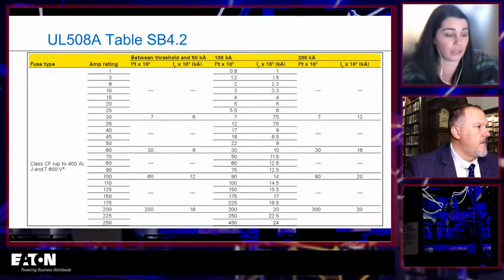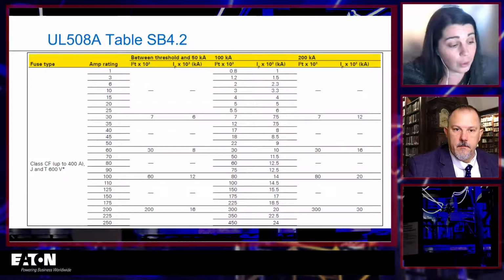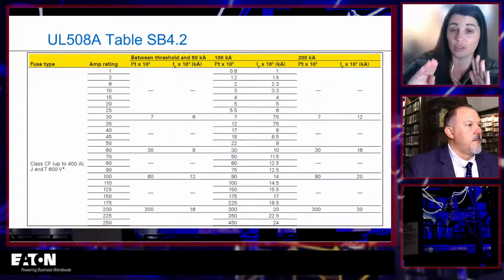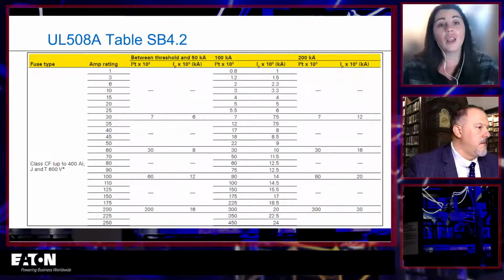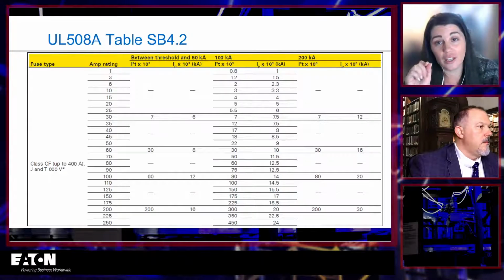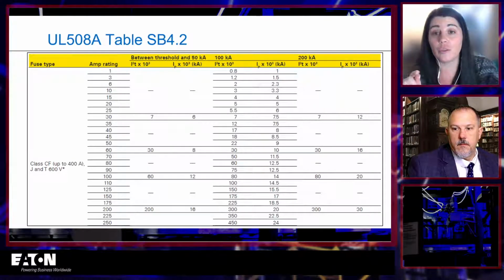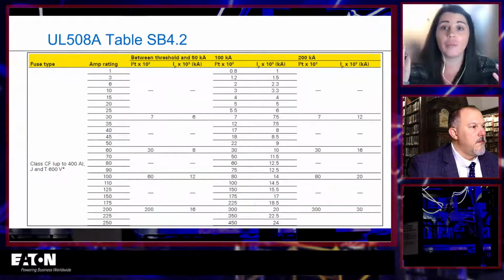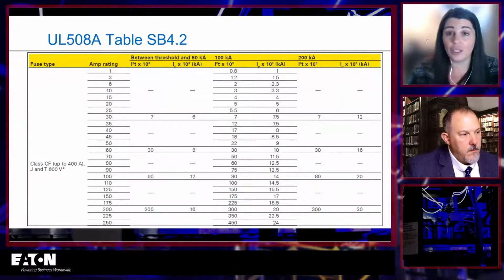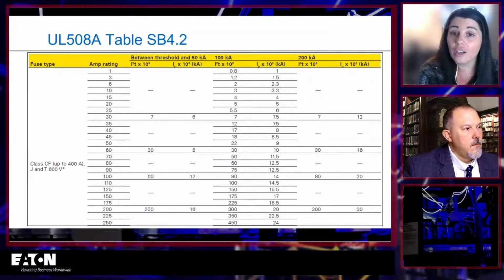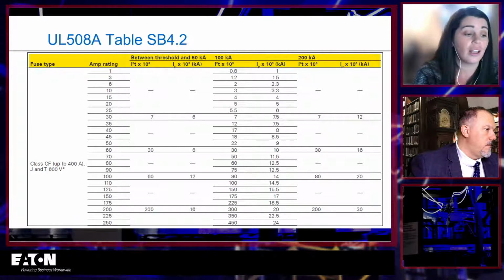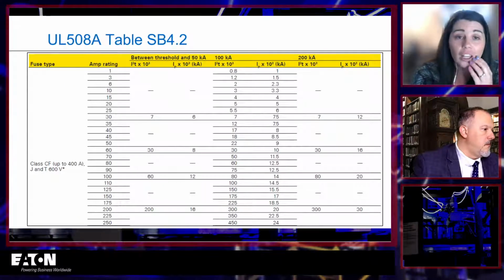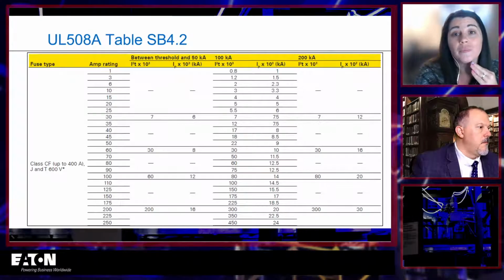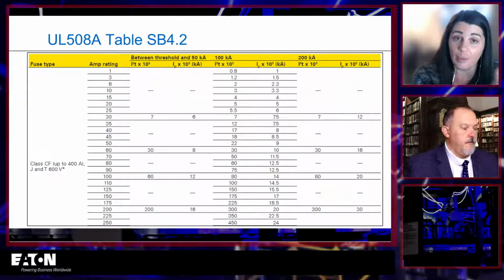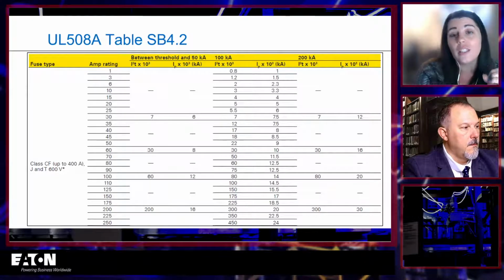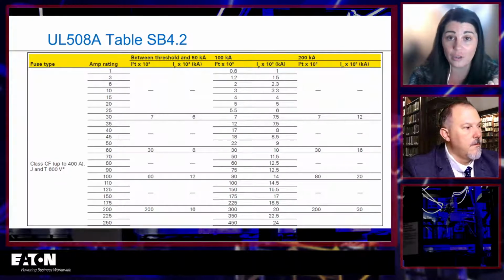is when we're using current limiting fuses within a UL 508A panel, or really within any panel where we're determining the short circuit current rating using UL 508A, we don't get to use the current limiting characteristics of the specific fuse that we're using. So I don't say, oh, well, I'm using a wonderful Bussmann LPJ-100, I'll go to the current limiting chart for that and determine what its let-through values are. Not how it works with UL 508A. UL 508A makes you use the ratings that are in table SB 4.2. And what these ratings are, we call these the umbrella limits for these fuses.